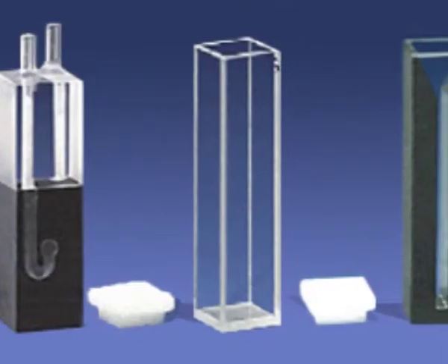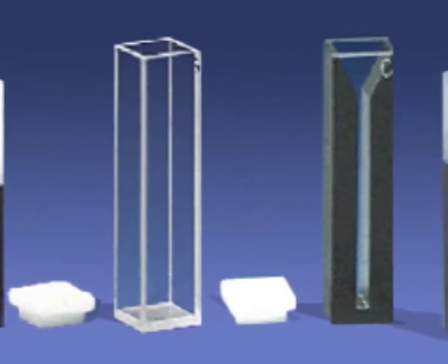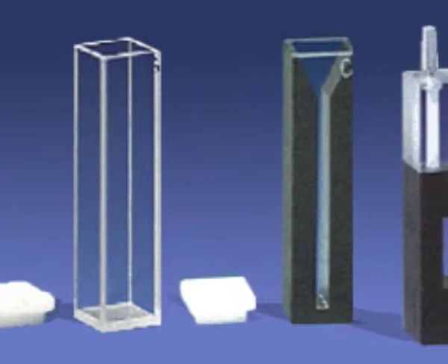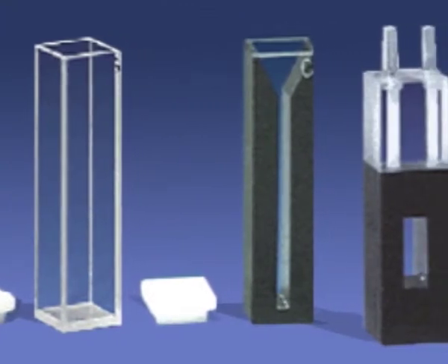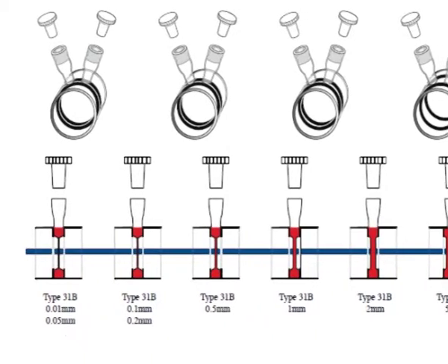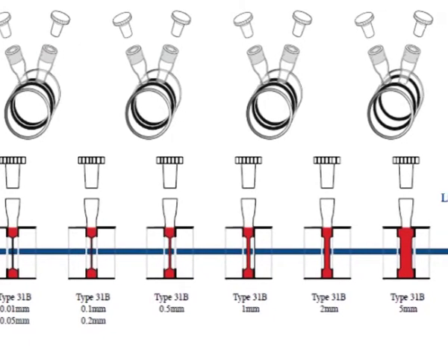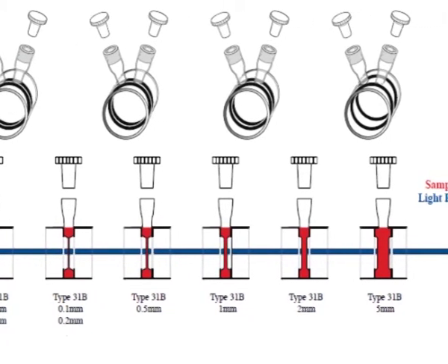The cell holding the sample should be transparent to the wavelength region to be recorded. Quartz or fused silica cuvettes are required for spectroscopy in the UV region. Silicate glasses can be used for the manufacture of cuvettes for use between 350 to 2000 nanometer. The thickness of the cell is generally 1 centimeter. Cells may be rectangular in shape or cylindrical with flat ends.